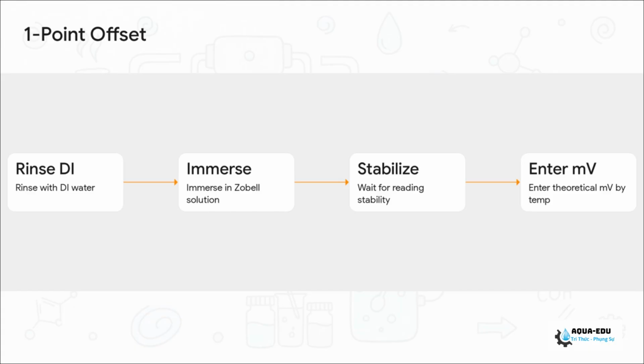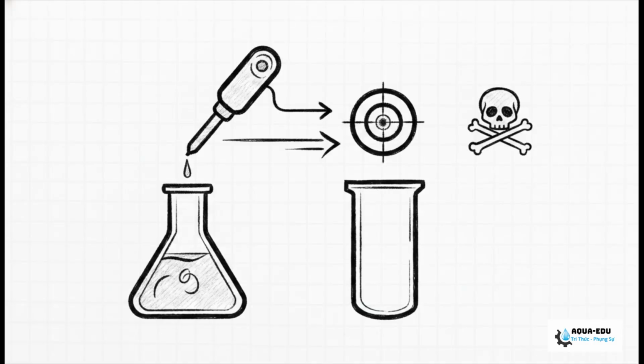Quick side note, if your specific system uses a standard hydrogen electrode reference instead, your target is actually going to be plus 430 millivolts. So always verify your reference type first. Now, as an optional second step, but one I really recommend for a more rigorous check, you can rinse the probe and check the span linearity in a second solution. You might use Light's solution, which sits around plus 475 millivolts, or maybe a quinhydrone saturated pH 4 buffer, which is about plus 264 millivolts. What you're looking for here is a variance of less than 15 to 20 millivolts from your theoretical target.